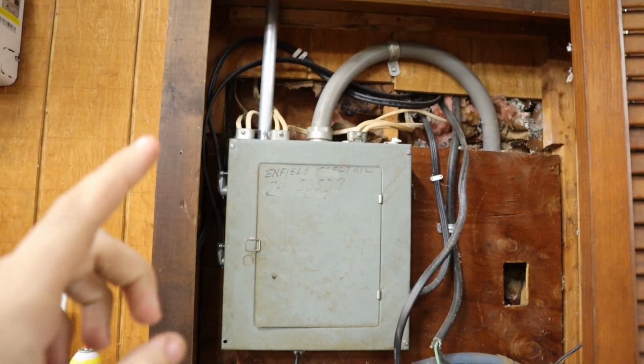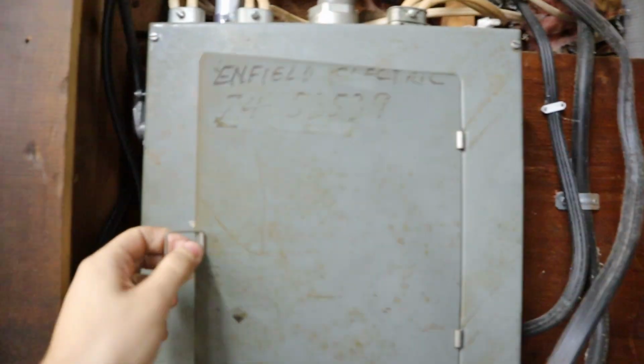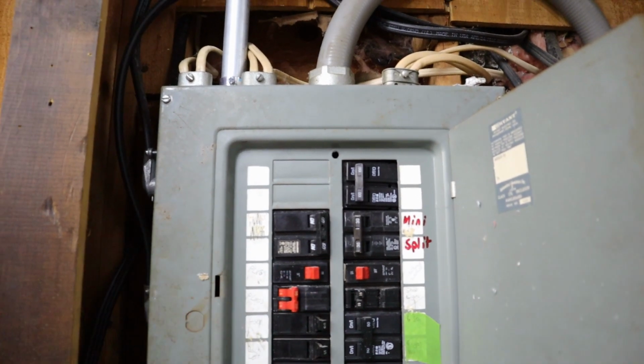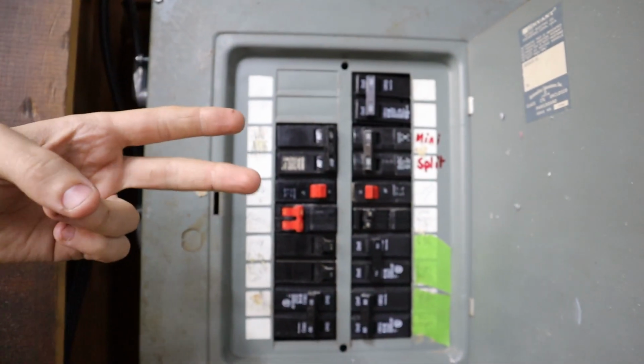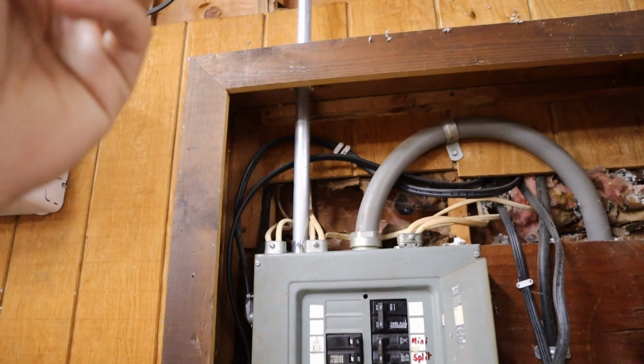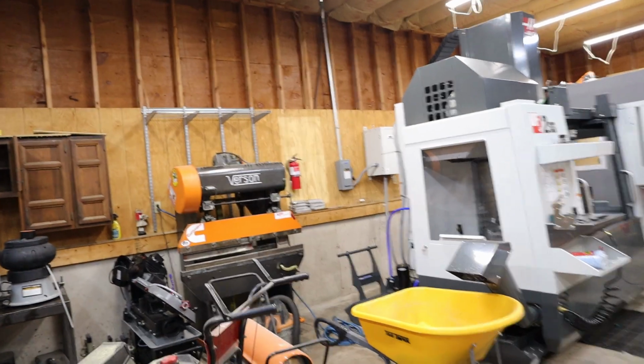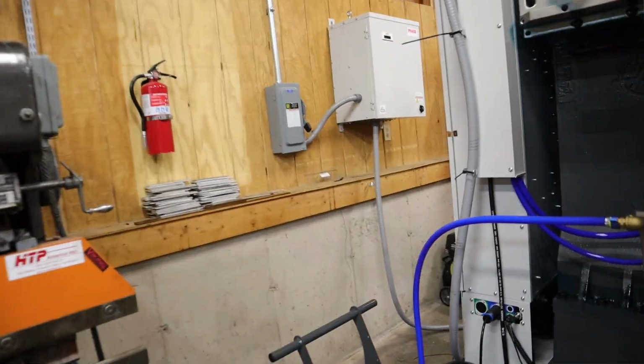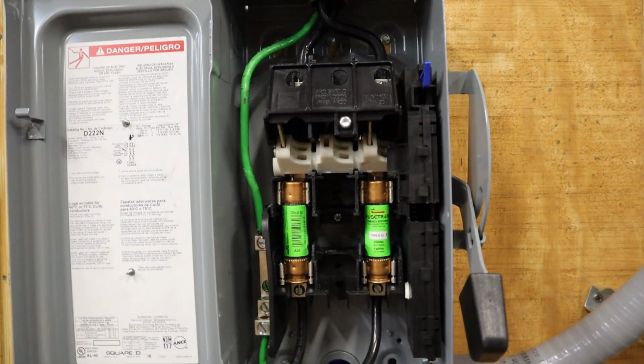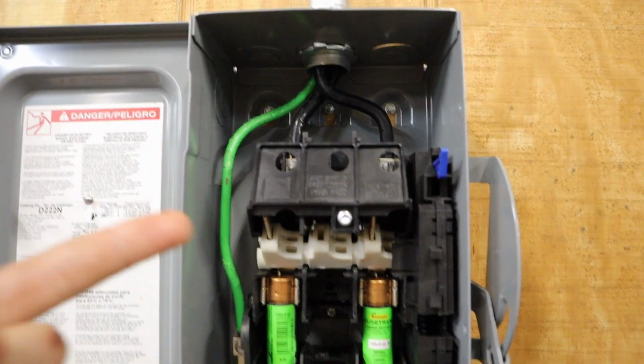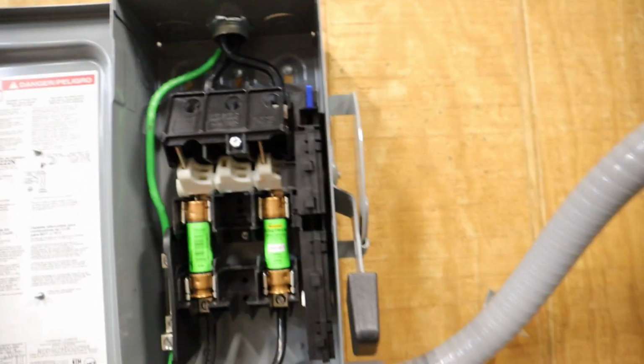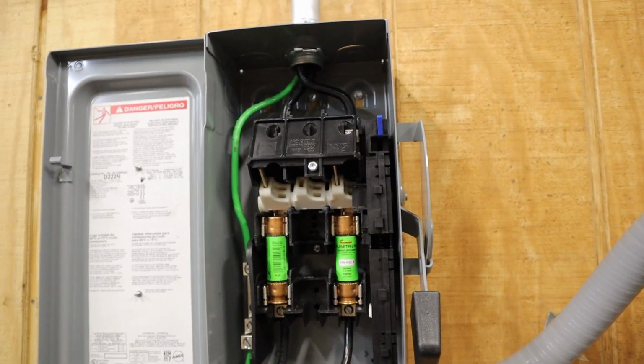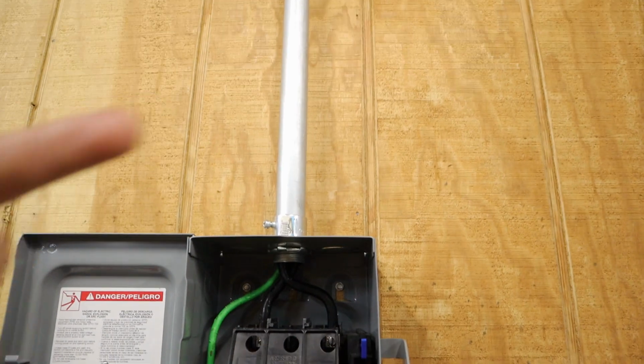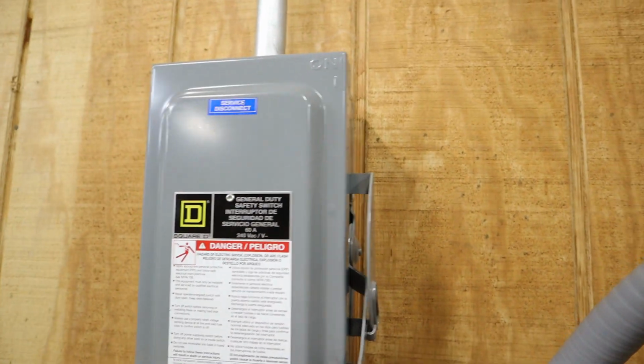There is 1/0 gauge coming from the house to this sub panel, and in this sub panel is a 100 amp breaker. The machine is running on a 60 amp single phase breaker, so 2 hot legs and the ground. They go up conduit with the ground, all the way across, lazily put right against the insulation, which is probably not to code. Definitely not to code, I mean. Those 2 legs, 2 gauge wire, come into this disconnect right here, and it's a 60 amp fuse. So you have your two hots, the ground, bonding bar, ground, and the 2 hots. The ground is a 6 gauge, which is obviously undersized, but the conduit also acts as a ground when properly installed. We got that going.